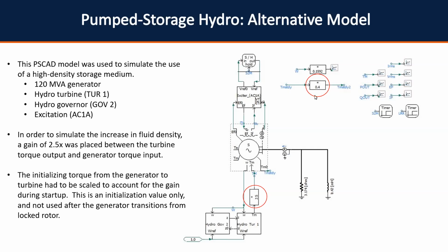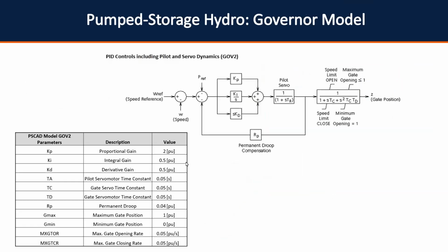There was one other thing: the initializing torque value here had to be adjusted. This was just at the start, to keep the machine stable when it transitioned to a real machine. It's at 0.4 right there, but it's only for initialization. The PID controls for this is the governor model with a PID controller. We have a similar controller for one of our sites, and I tried plugging some of those variables in. That did not work. These were more or less trial and error, understanding what the changes are going to make, and then tuning it down to where it worked. The PID governor seemed to do the best.